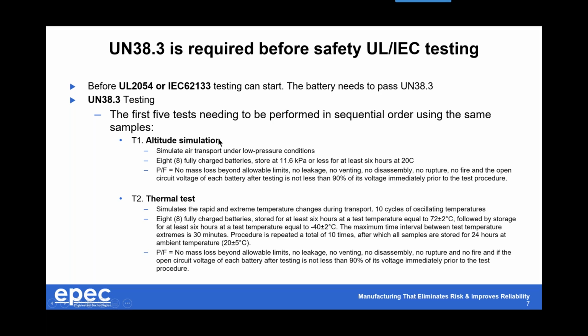First is the altitude simulation test, which simulates transport under low pressure conditions—like losing cabin pressure, or being shipped in an unpressurized part of the plane. Under near-vacuum conditions, they want to make sure the cells and electronics don't fail. The samples are stored for many hours at room temperature, and afterward you'll notice the pass-fail criteria for many of these first 5 tests is no mass loss—they weigh the battery before and after and check the percentage mass loss against allowable limits.